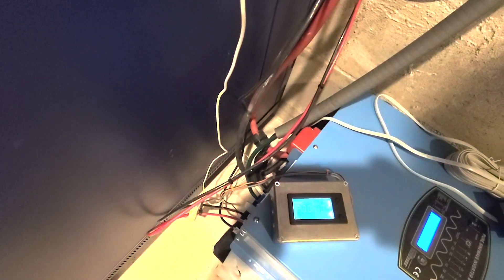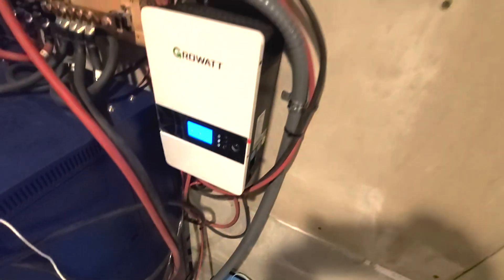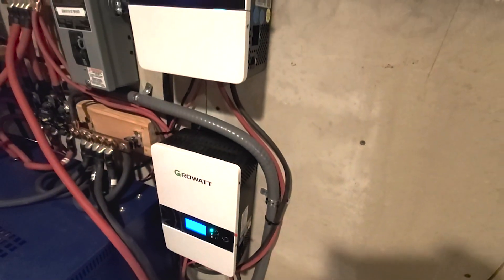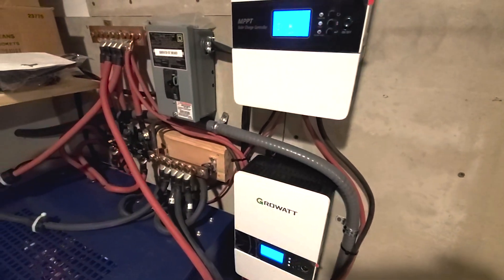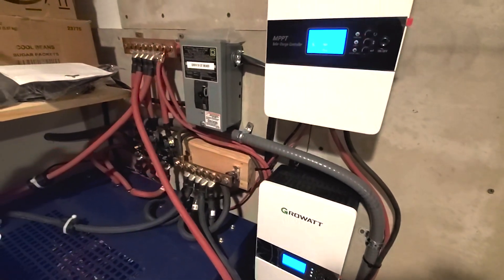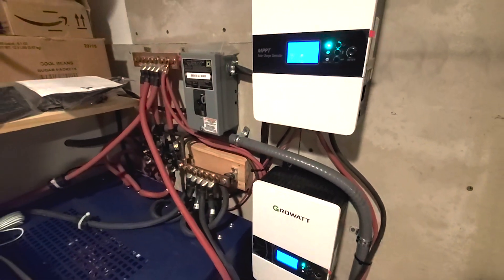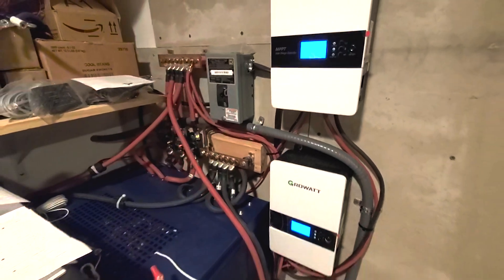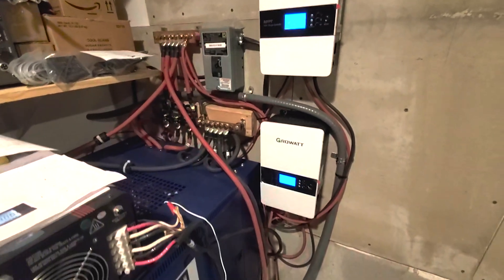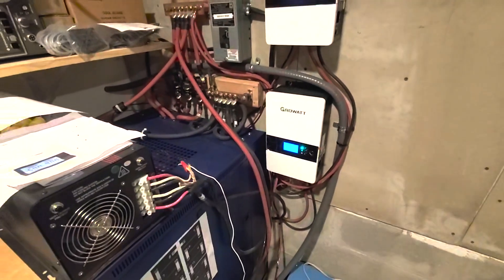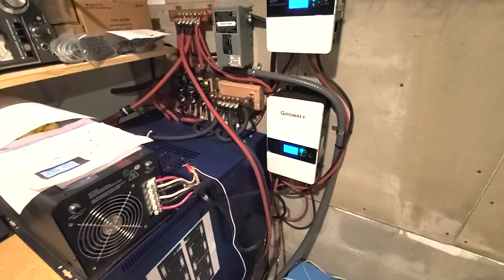The main unit is now connected with 4 gauge wire inside of a 3/4 inch seal tight conduit to a 100 amp breaker in the main panel.